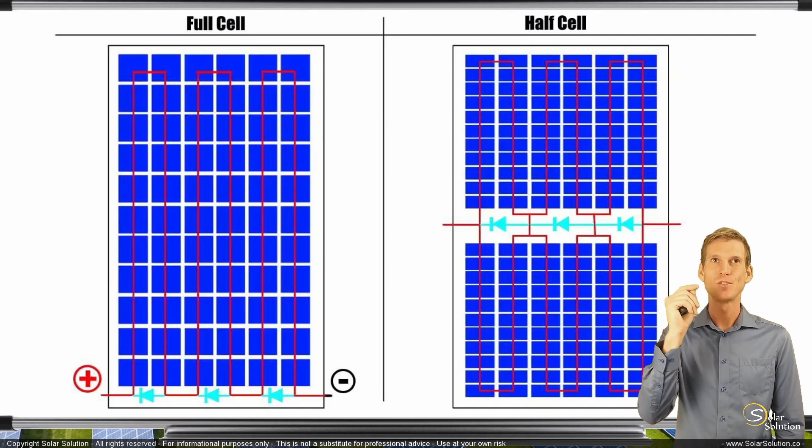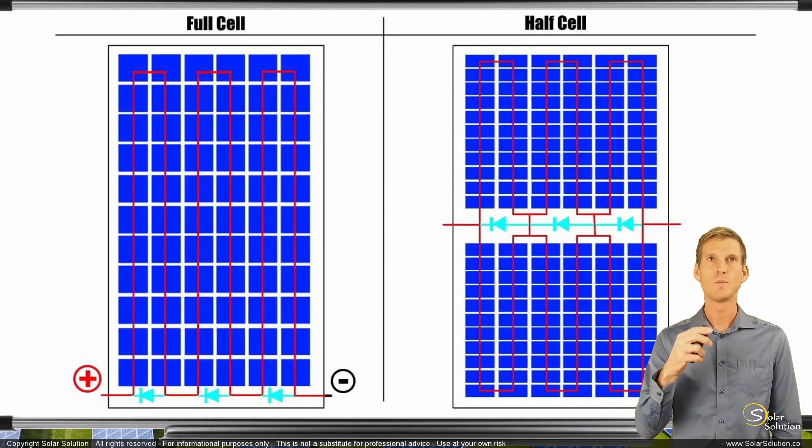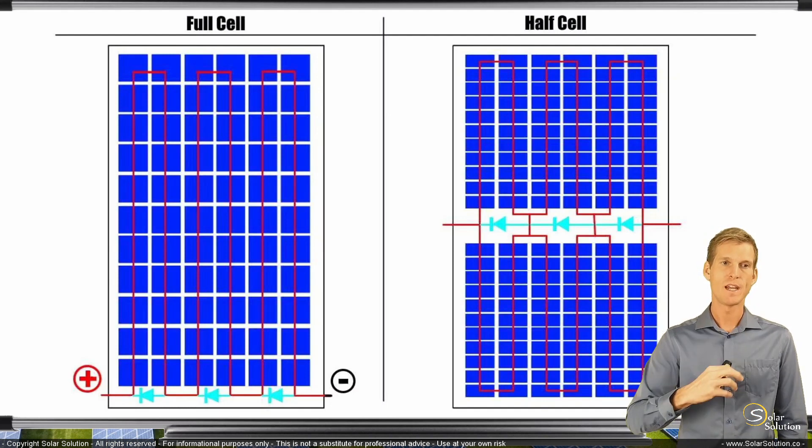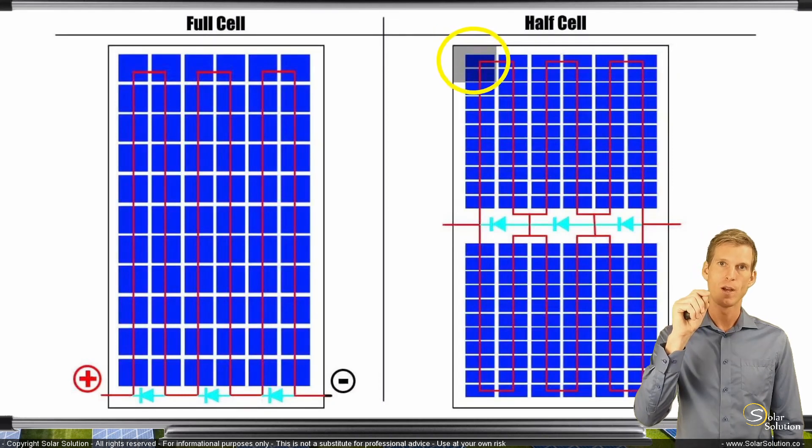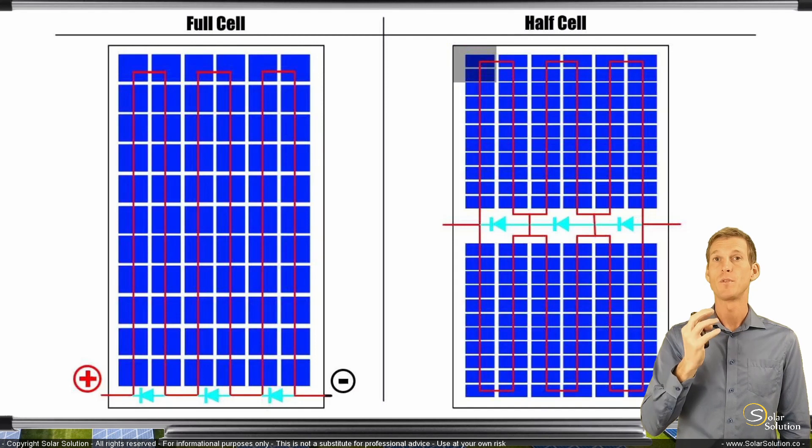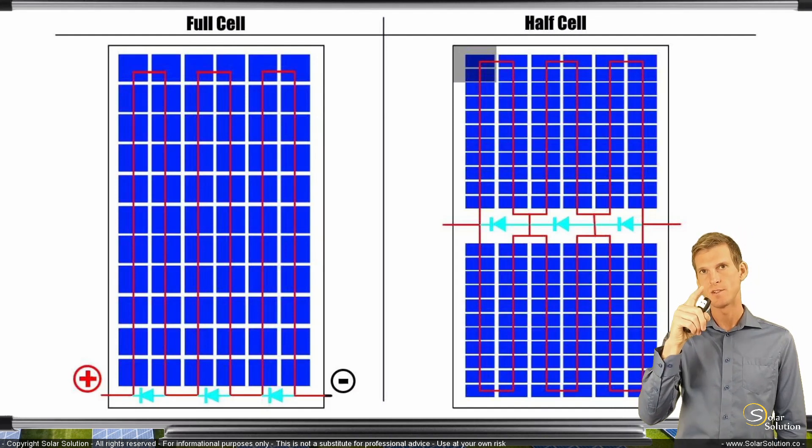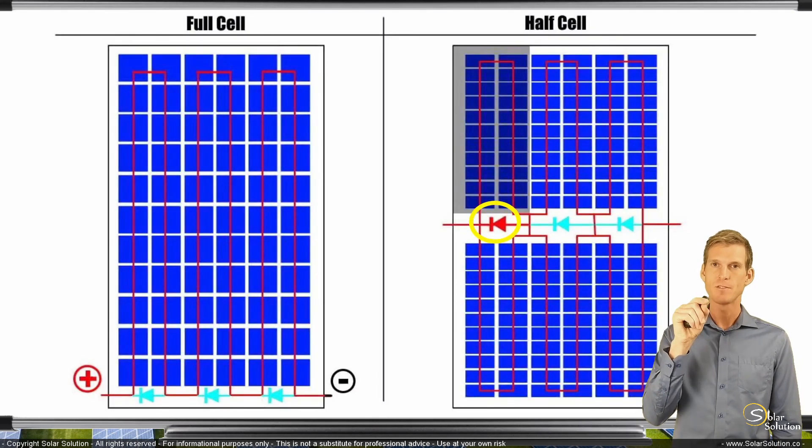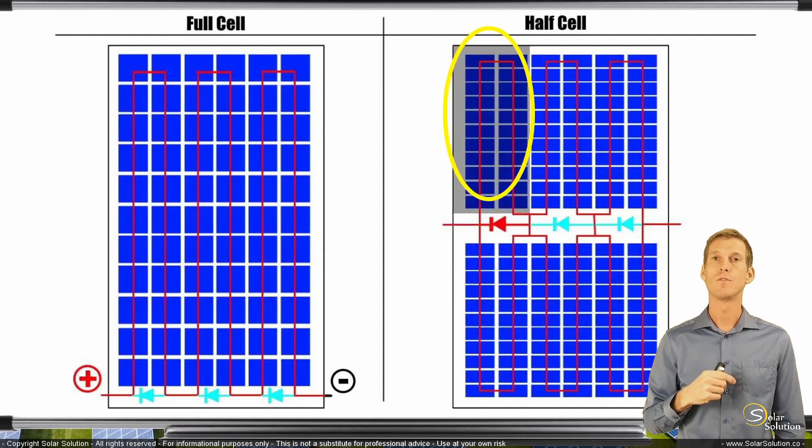And now let's see what happens if we get local shading or some kind of malfunction or underperformance of one of the photovoltaic cells in this module. Let's assume we have a similar situation as we had with the full cell regular photovoltaic module. We're getting some kind of local shading on the panel, all the way at the top left on the module, whereby some of the cells all the way in the top there are not operating anymore. And therefore, you're affecting the whole string. But now the first bypass diode will be activated and will redirect the current. And you can see that as a result, that whole loop on the top left is not functioning anymore, not contributing anymore to the overall power output of the module.